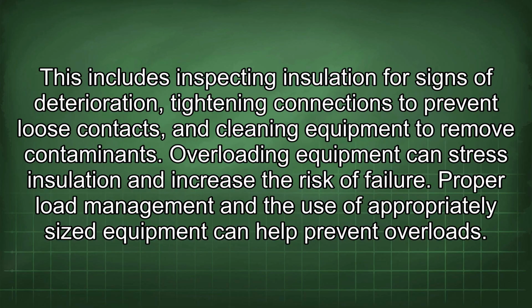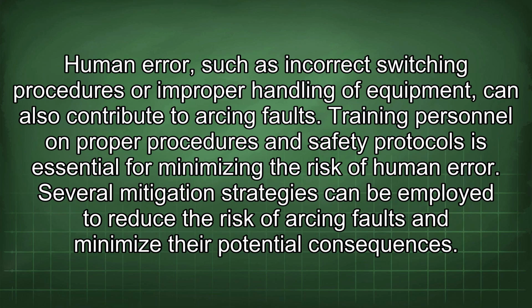This includes inspecting insulation for signs of deterioration, tightening connections to prevent loose contacts, and cleaning equipment to remove contaminants. Overloading equipment can stress insulation and increase the risk of failure. Proper load management and the use of appropriately sized equipment can help prevent overloads. Human error, such as incorrect switching procedures or improper handling of equipment, can also contribute to arcing faults.